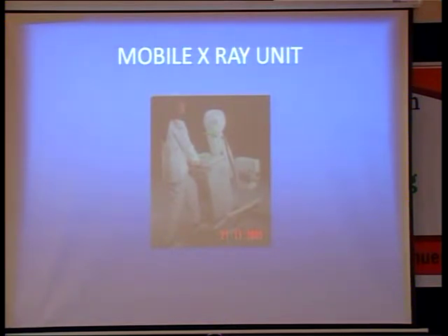Previously it was 30 mA, now even 100 mA units are being sold, and somewhere 150 to 200 mA is also there. With a bedside X-ray, when the machine's mA is low, the quality will be very poor, because most sick patients will not be able to cooperate. If the exposure takes 1 second or so, it will be blurred. So a millisecond exposure is needed, so a higher mA machine is needed for mobile X-ray. This will be helpful for ICU patients or surgical patients, or patients who may not be able to come to the department. Then it will be very useful.